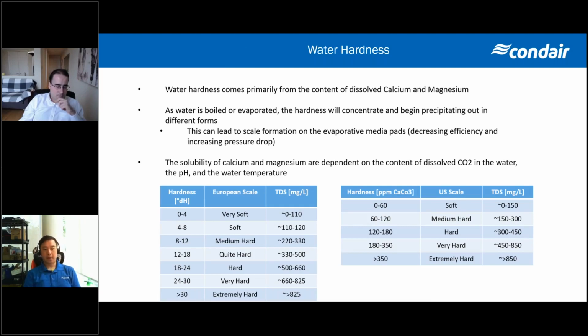What we're primarily concerned about here is water hardness. The water hardness is primarily coming from dissolved calcium and magnesium that's in that supply water. As we boil that water, or in this case, as we evaporate it into the air, that hardness will concentrate, and once it hits a specific concentration, will begin precipitating out in different forms. In general, what we see that form as is scale formation or buildup on the evaporative pads themselves. And what that can do is decrease efficiency, because we lose surface area on the media, and we also see potentially an increase in pressure drop, because that scale starts blocking off some of the flute configurations on the pads themselves that allow the air to pass through.